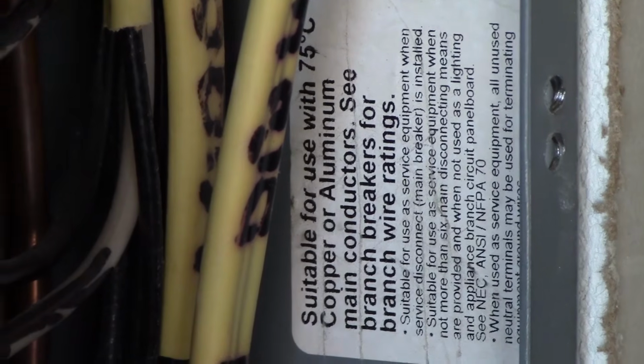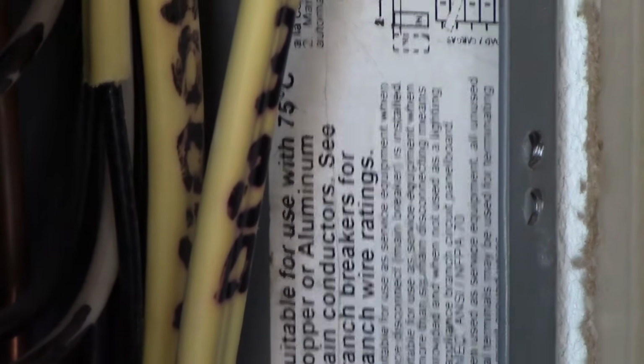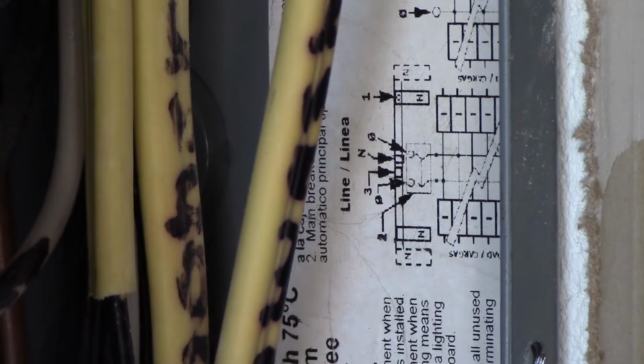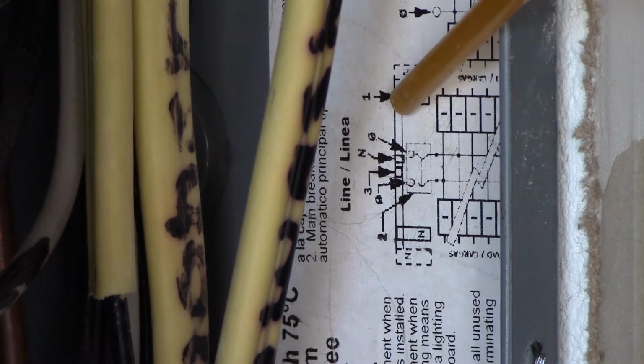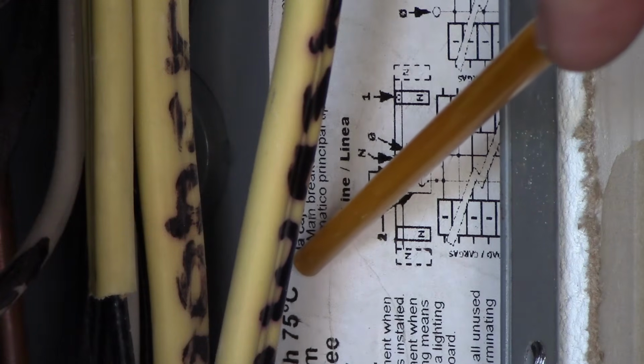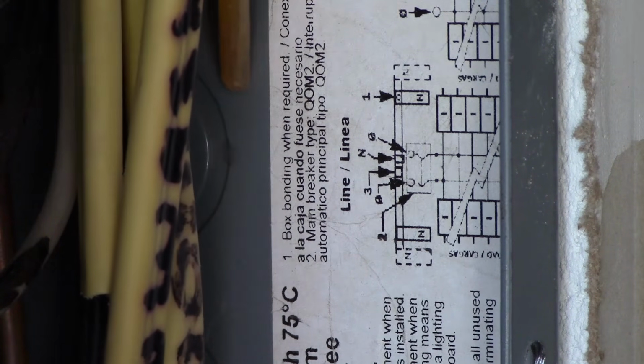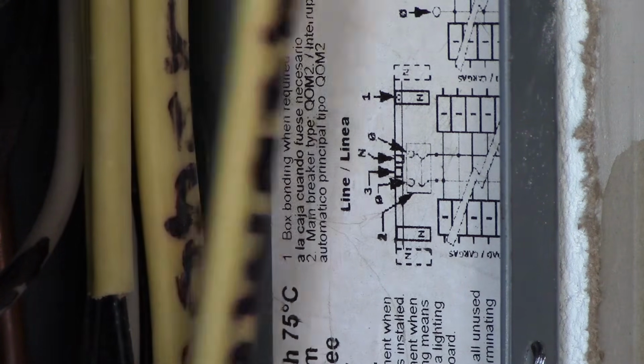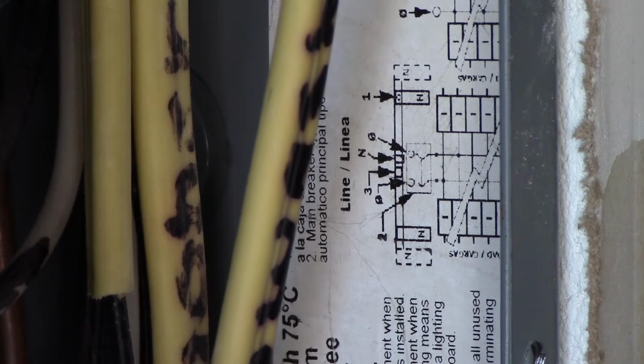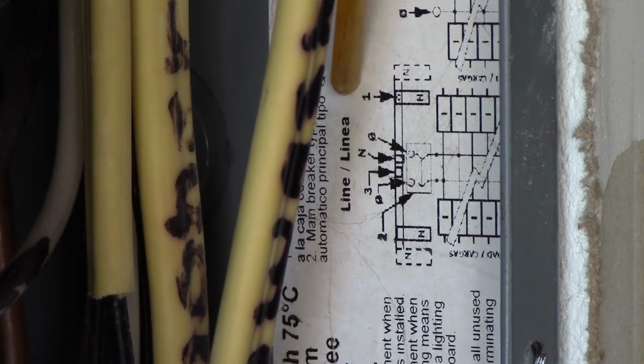The other thing we want to look at, up here a little bit, is right there. This is kind of unique to newer panels. You won't find this in a lot of the older panels, or you might find some old diagrams. It should tell you where your main bonding jumper goes. In this case, right here, it has a number 1. If you take the number 1 and look up here, it says that number 1 identifies where the bonding is made when required. And of course, this being a main panel, it does require that main bonding jumper to connect the neutral to the enclosure, and all the equipment grounding conductors and the grounded conductor to the enclosure. So it's all tied together, which you don't want downstream, but you do want at a main panel. Here it tells you where to do it, and right there it says where that main bonding screw goes.